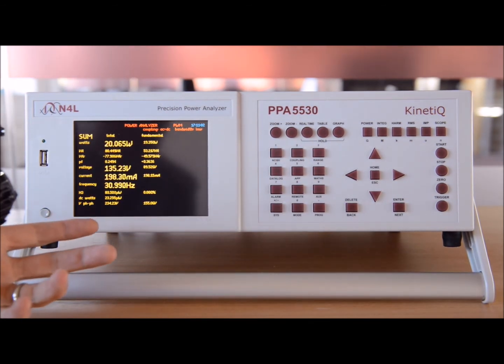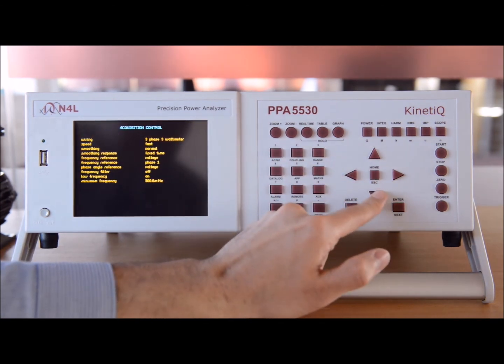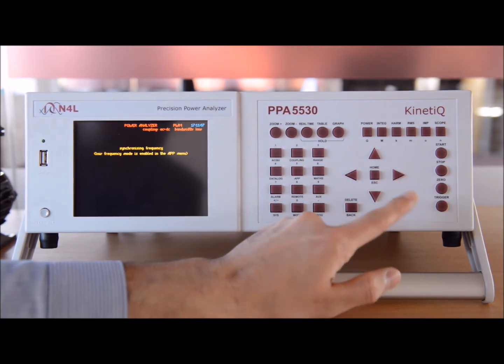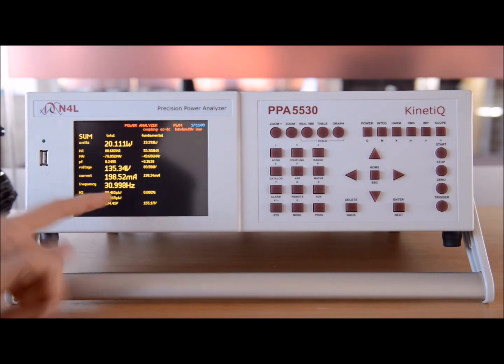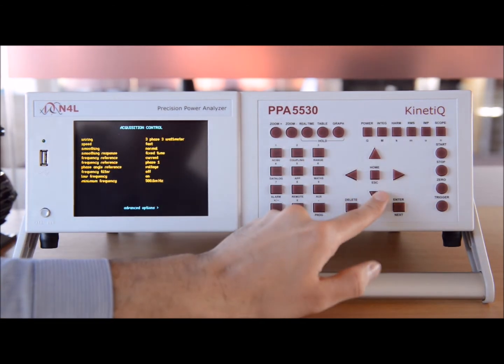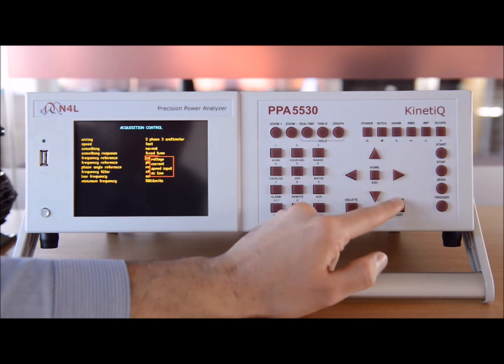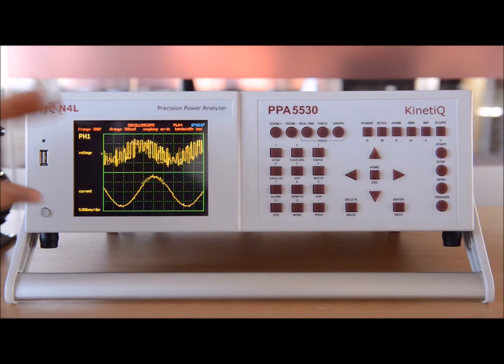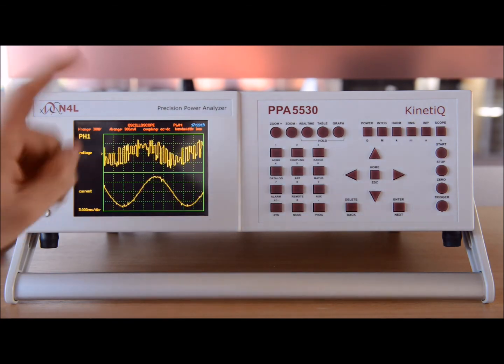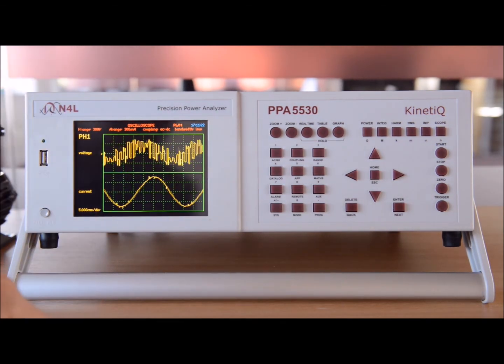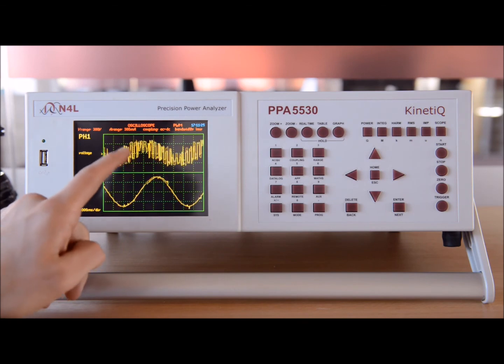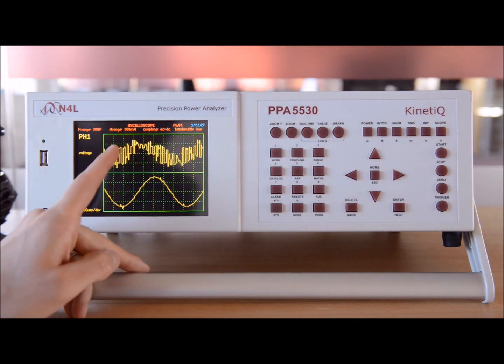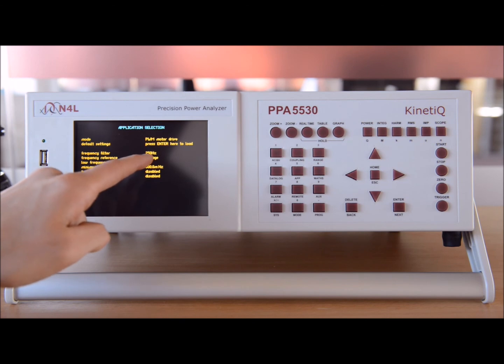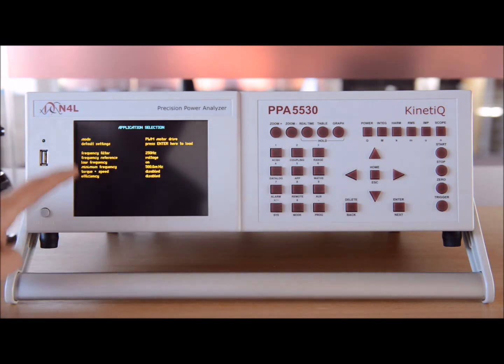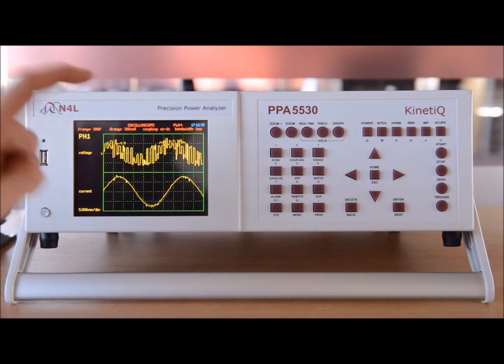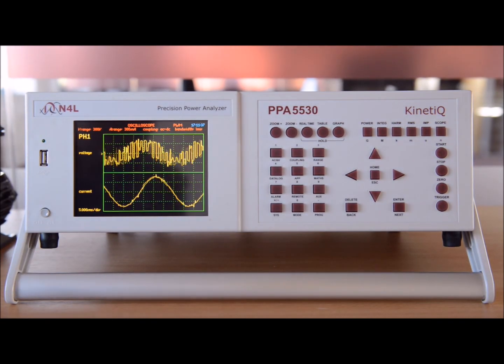Now, just a quick example, if I wanted to use the current as my frequency reference, I can, and we'll get a similar result. However, I like to leave it as voltage, because it means that as that current gets really low, as the load goes off, we've still got a voltage there and we can still extract the fundamental with the DFT. Now do note that this is still a wideband measurement. Just because we have a 250 Hertz frequency filter for the frequency synchronization, we are not putting the filter in there for the wideband power measurement.